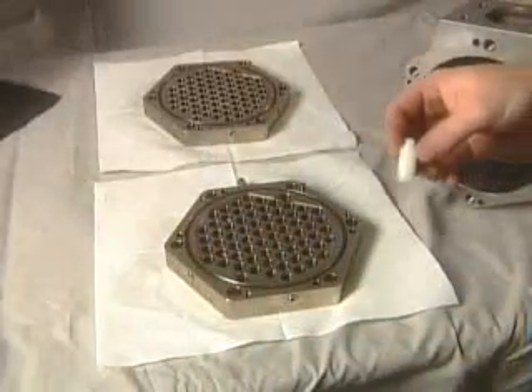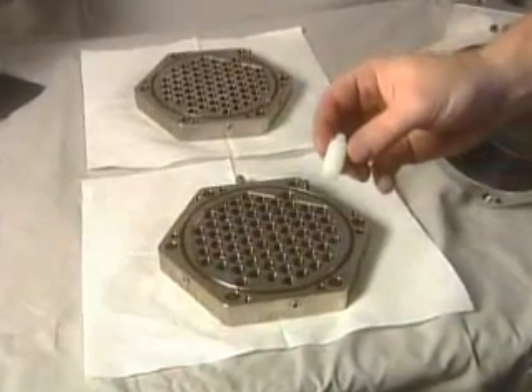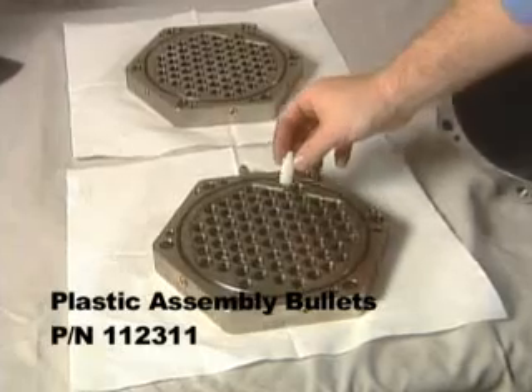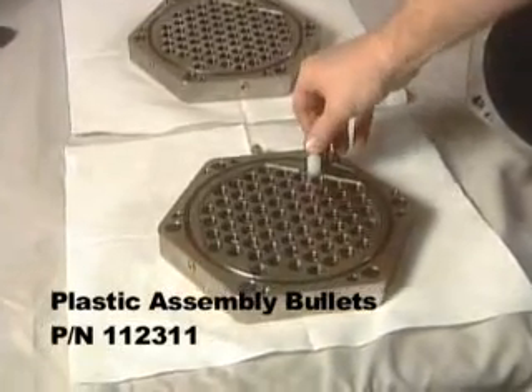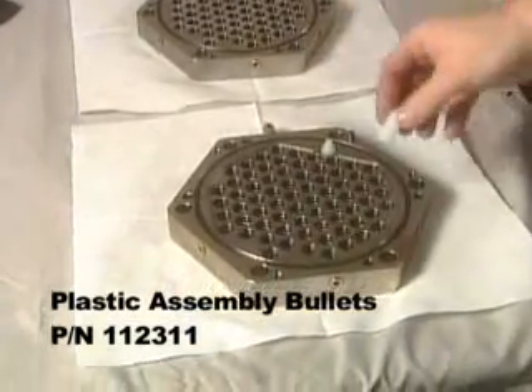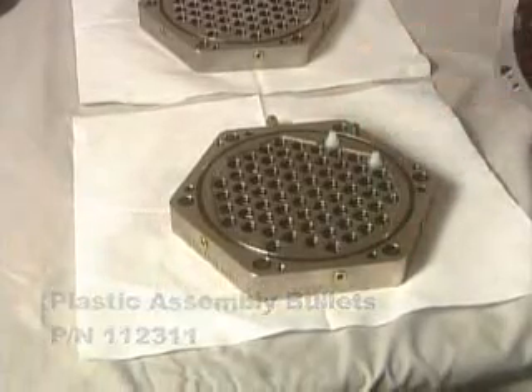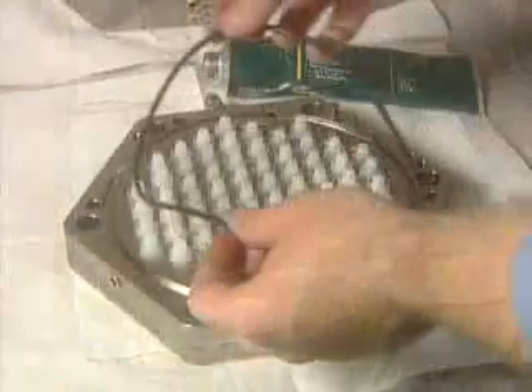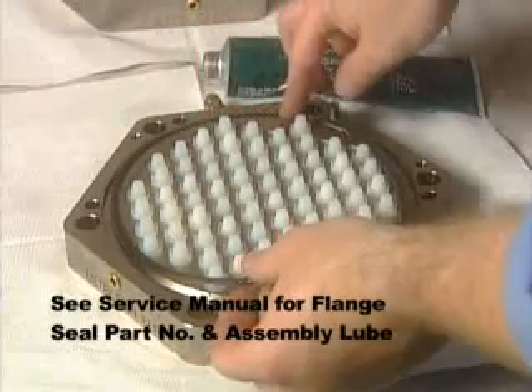Lay both header plates down on a clean surface with the alignment pins facing up. Install the plastic assembly bullets into all the tube holes in both header plates. Tapered ends of bullets go into the holes first. Install new header-to-end flange seals into the header plate.